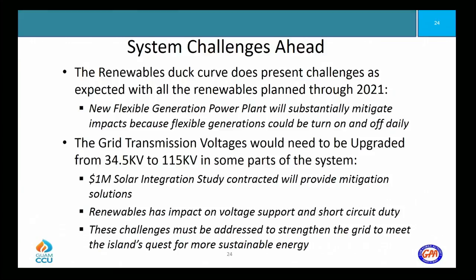There are challenges. There's what they call a duck curve, I'll show you that in a minute, with all renewables planned, and the power plants today cannot work with the duck curve. That's why new flexible generating plants will substantially mitigate the impacts, because flexible generation can be turned on and off, while our generators today you can only back down so much before you have to take them off. Like the Cabras steam plant, you can only back it down to about 35 megawatts from 60, and when you're at 35 you have to start taking it off the line. To put it back on the line again takes about 6 to 8 hours. It's not like you can turn a switch like a car. That's why flexible generation makes a difference and works with renewables, while our system today cannot.